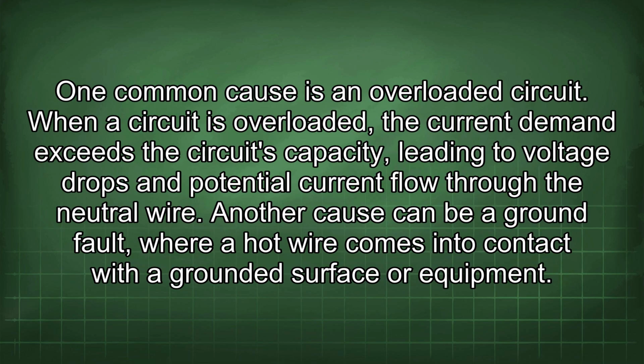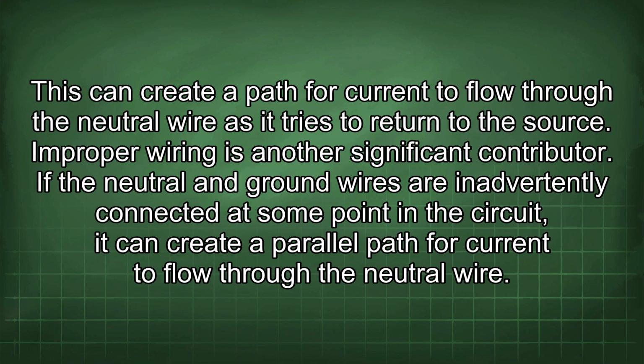One common cause is an overloaded circuit. When a circuit is overloaded, the current demand exceeds the circuit's capacity, leading to voltage drops and potential current flow through the neutral wire. Another cause can be a ground fault, where a hot wire comes into contact with a grounded surface or equipment. This can create a path for current to flow through the neutral wire as it tries to return to the source.